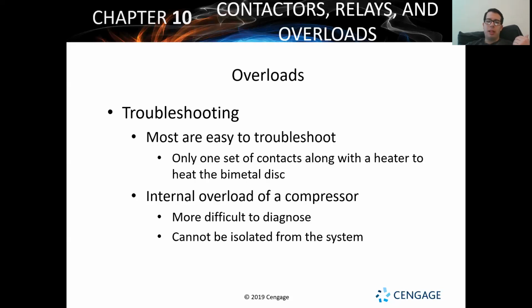So that's a really common cause of an overload or overheating on a compressor in the summertime, especially because it's running, it's got that air conditioning going, and it's pumping that refrigerant around and around. The only thing cooling that compressor off is pretty much the refrigerant going through it. That's it: airflow and the refrigerant. The airflow really doesn't help too much, because it's increasing in heat as it goes across that condenser coil and surrounds the compressor. Now all that heat is sitting right on top of it, and all that's cooling it off is the refrigerant it's compressing. You've got that low pressure, low temperature vapor coming in from the evaporator cooling the compressor, but only slightly.